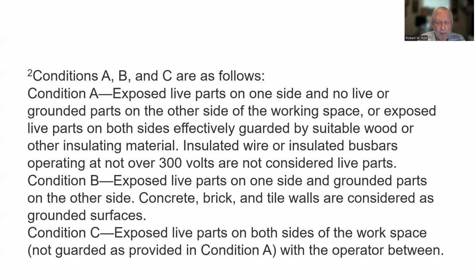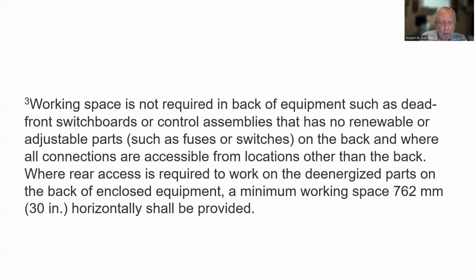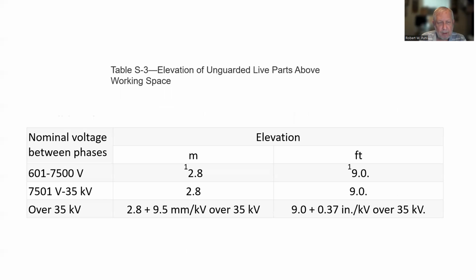Condition B, exposed live parts on one side and grounded parts on the other side. Concrete, brick, and tile walls are considered as grounded surfaces. Condition C, exposed live parts on both sides of the workspace, not guarded as provided in condition A, with the operator between. And then note 3, working space is not required in back of equipment. Okay. That was kind of the same as that last one. If there are de-energized parts, or rear access is required to work on de-energized parts, you need 30 inches in the back too.